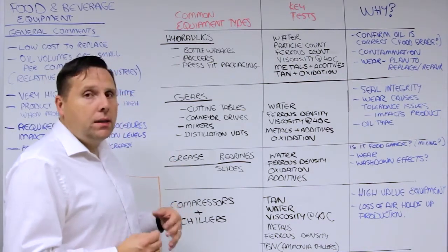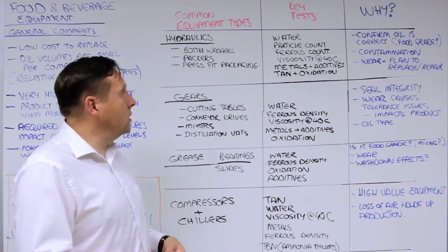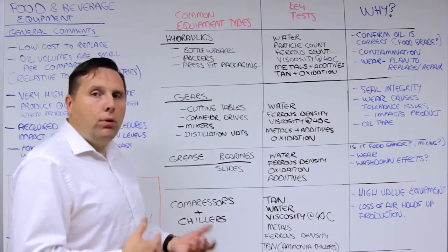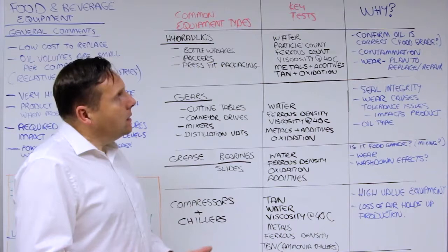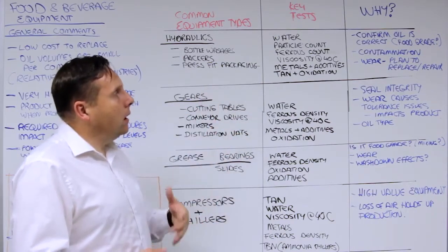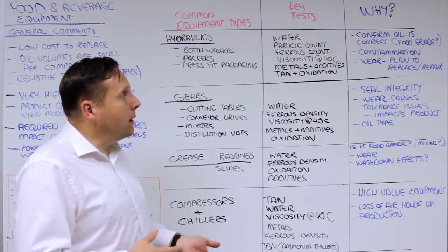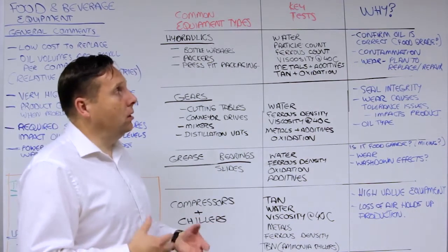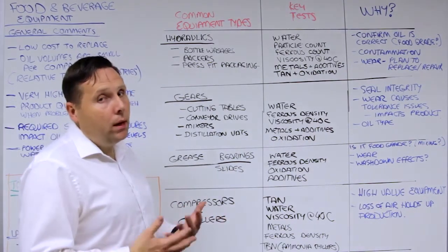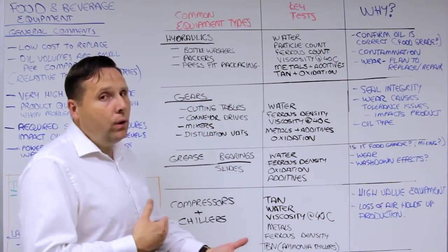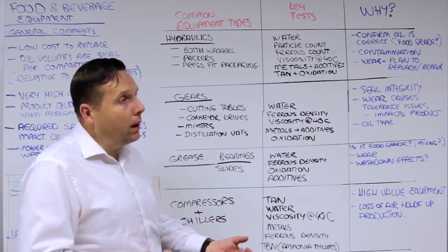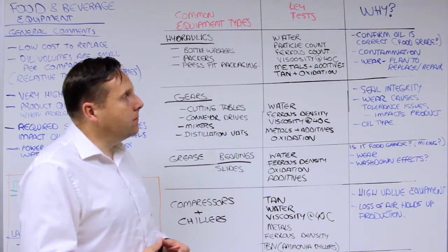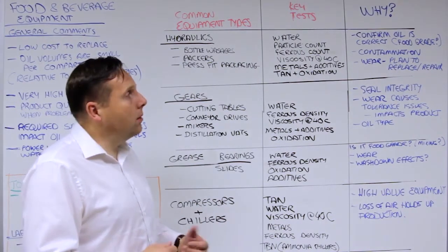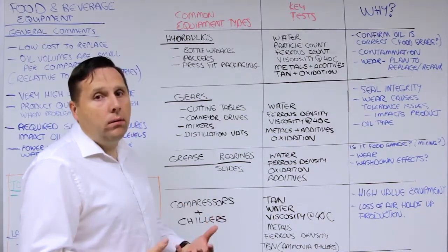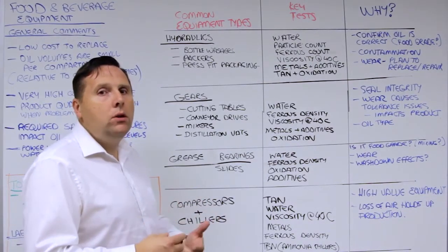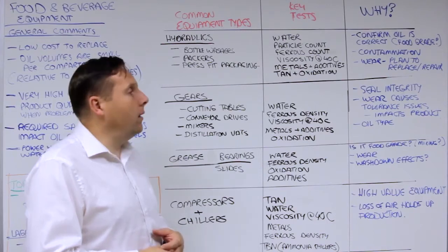In the case of hydraulic systems, they're used in a lot of different applications: bottle washers, packers, press fit packaging systems. The key tests we want to worry about are water, particle count, ferrous count, viscosity, metals and additives, TAN and oxidation. Why? Well, we're always worried about making sure that's the right oil that's present. Obviously, if we have a food grade oil and we put the wrong oil in there, that's a high risk to the process. We're worried about contamination getting into the system. And wear is also a concern. If there's any wear at all, we need to know when to actually schedule the replacement of that system.